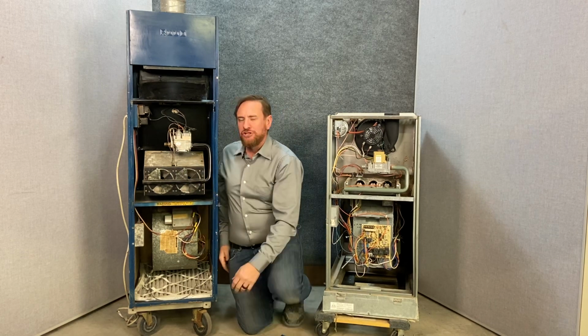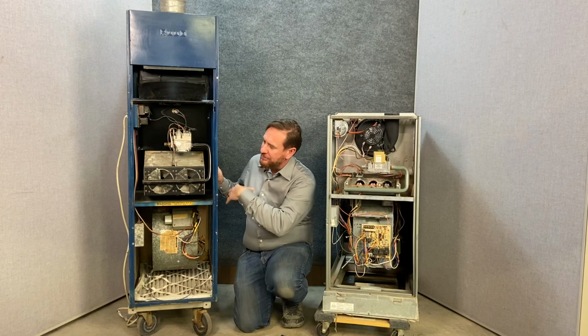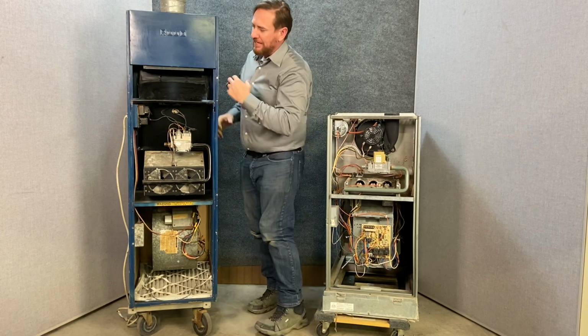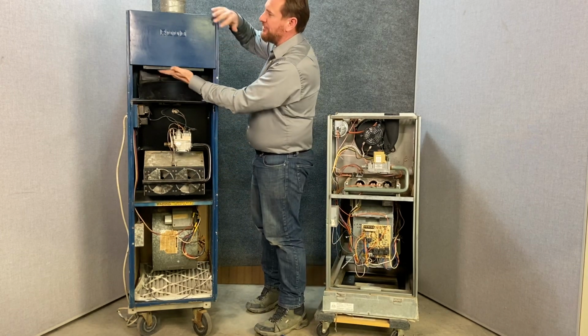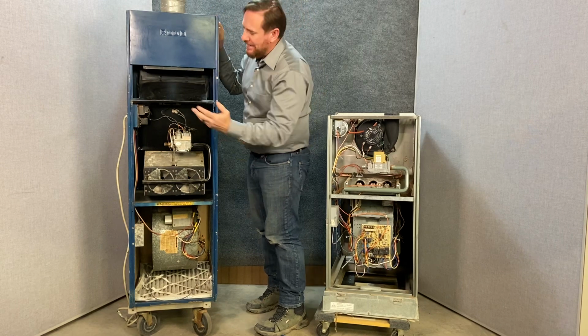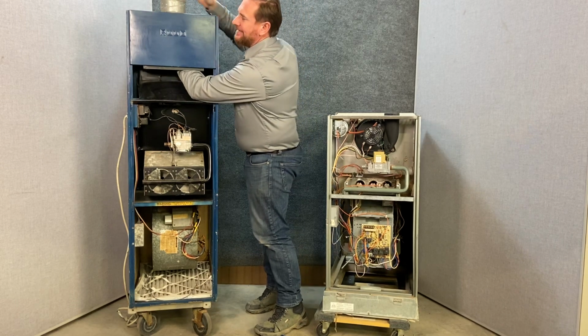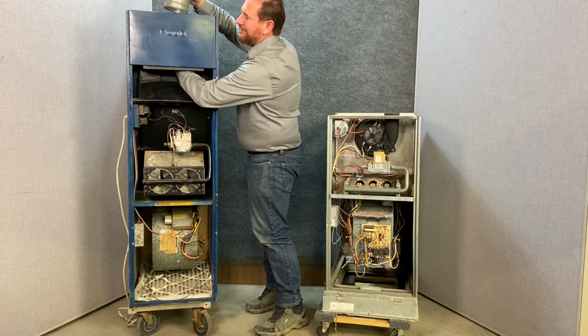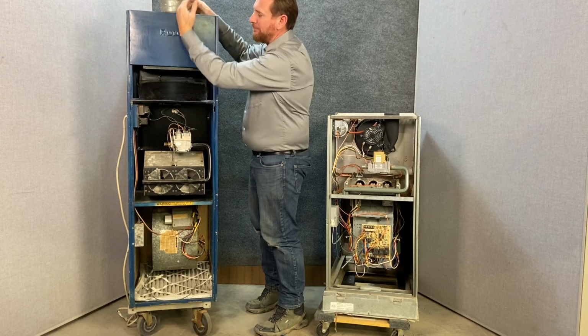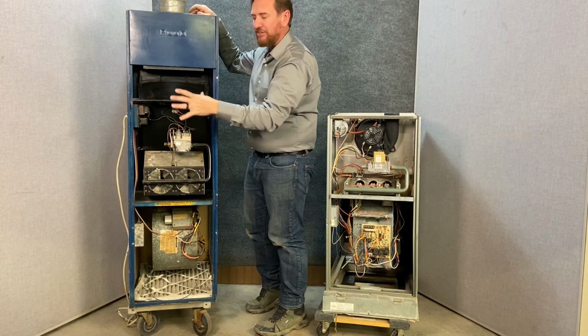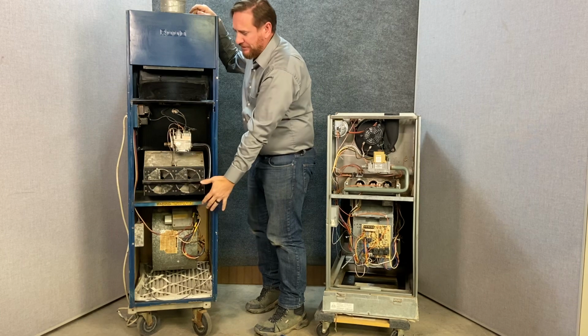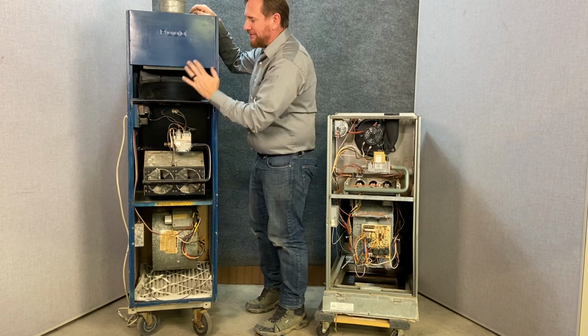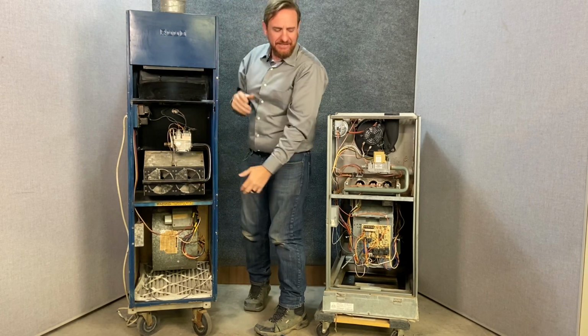Let's also talk about the draft. As this furnace burns, it just naturally drafts up. It collects at the top of the heat exchanger and it just naturally drafts out the flue pipe. I can literally stick my hand up inside of this flue pipe and that's all there is. So a windy day is going to blow that combustion gas back into this closet. It could seep back through any little cracks into the house. It was a very simple design, but there were no safety aspects.